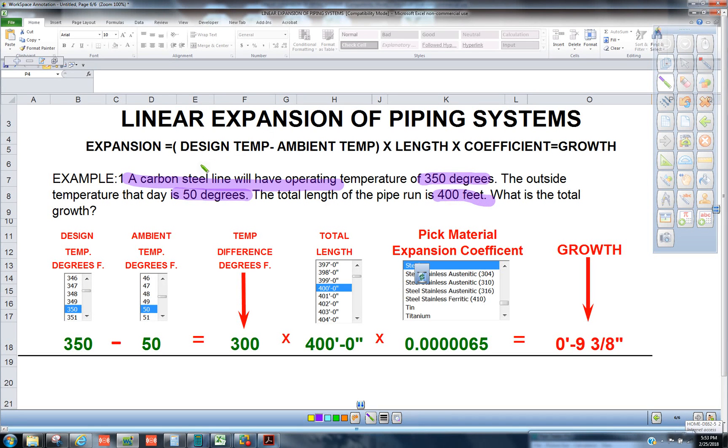So what we got to do is we have to take the design temperature minus the ambient temperature, giving us the temperature difference, by the linear footage, and then we're going to multiply it by this coefficient number.